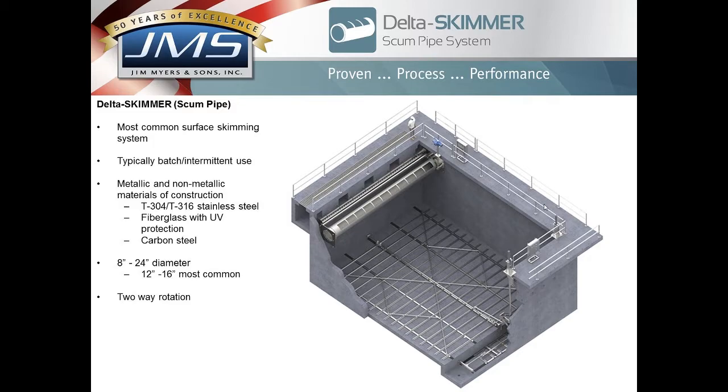The most common diameters are 12 inch to 16 inches, and the diameters are driven by a number of factors. They can be driven by the width of the basin. Most commonly, they're driven by the change in water elevation from minimum to maximum throughout a day. The greater that change in water elevation, the greater the diameter of the scum pipe needs to be in order to accommodate that change. Typically, scum pipes rotate both directions because inevitably scum accumulates behind the scum pipe as well. So you want to be able to, on a batch or intermittent basis, collect the scum behind.